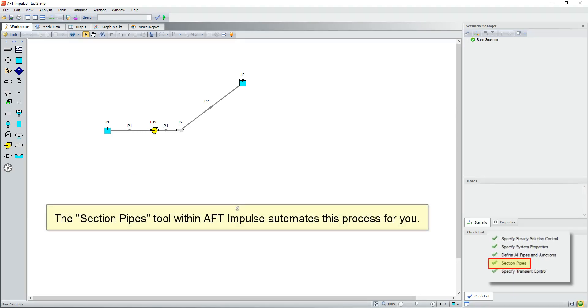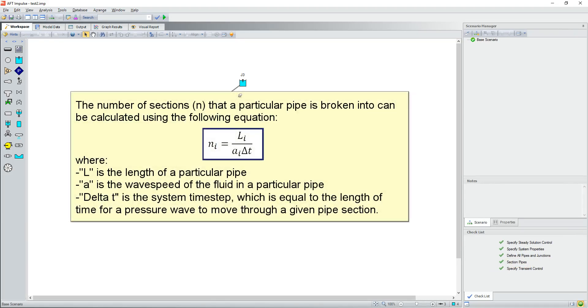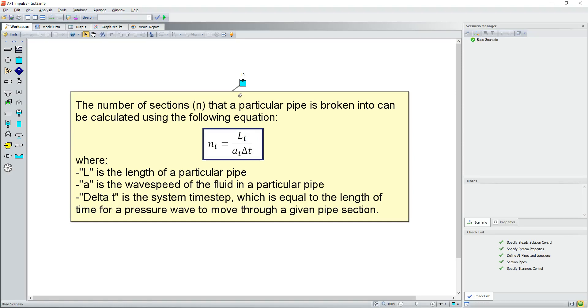The section pipes tool within AFT Impulse automates this process for you. The number of sections N that a particular pipe is broken into can be calculated using the following equation: N sub i equals L sub i divided by A sub i times delta T, where L is the length of a particular pipe, A is the wave speed of the fluid in a particular pipe, and delta T is the system time step, which is equal to the length of time for a pressure wave to move through a given pipe section.